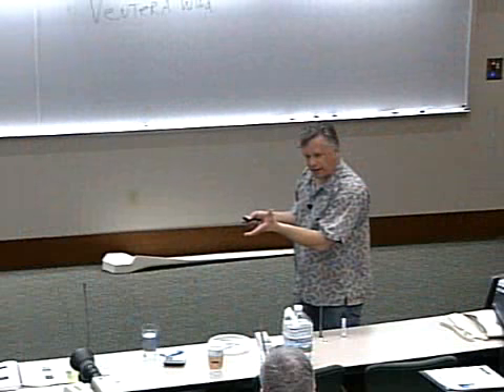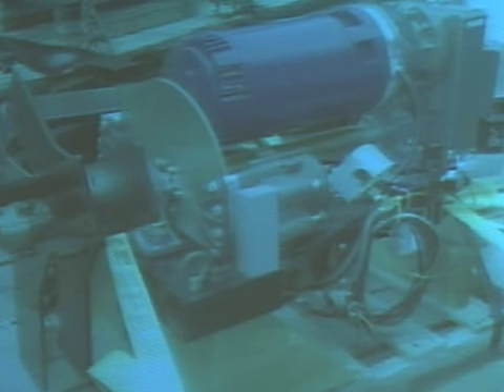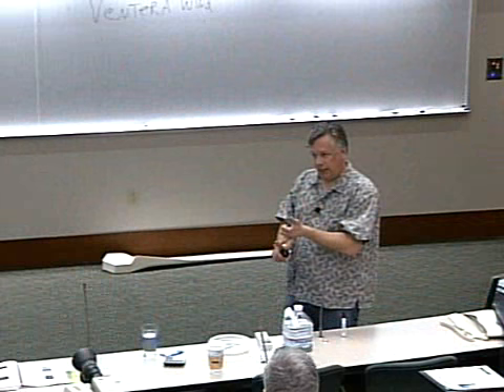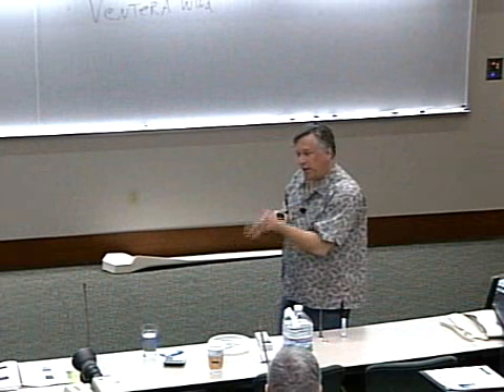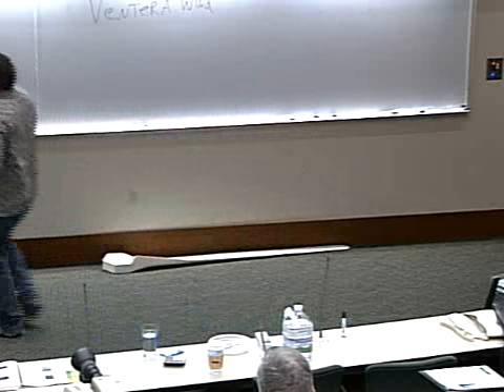At 200 and some RPM, the wind is going to take over. As the wind tries to drive the rotor faster, the power is no longer going to the rotor, it's going from the rotor to the drive shaft, to the gearbox, to the motor. Now our motor is a generator. We're trying to overspeed that motor, but we're locked in voltage and frequency with the utility. So as we try to overspeed the motor, we get amperage output instead, and the greater the wind speed, the greater the amperage output.